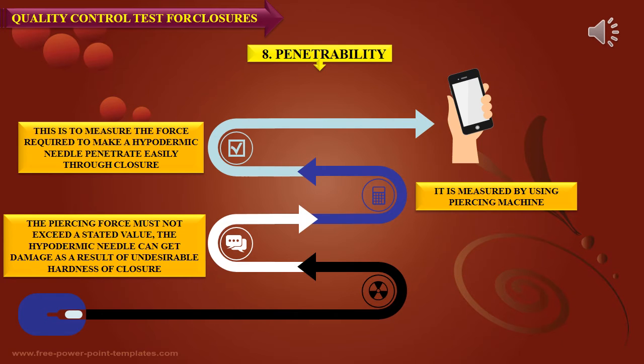The penetrability test measures the force required to make a hypodermic needle penetrate through the closure. The piercing force must not exceed a stated value, as the hypodermic needle can get damaged due to undesirable hardness of the closure. It is measured using a piercing machine.